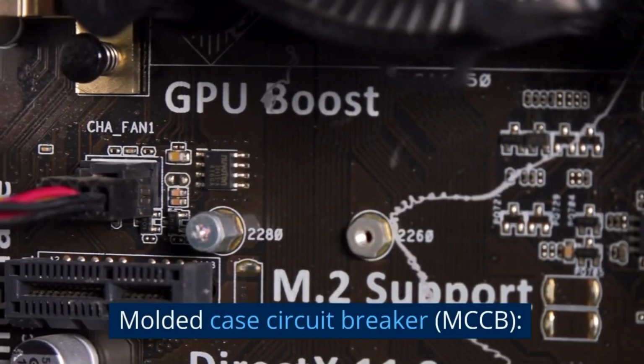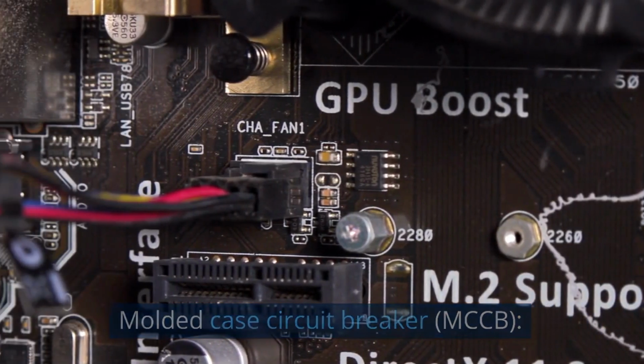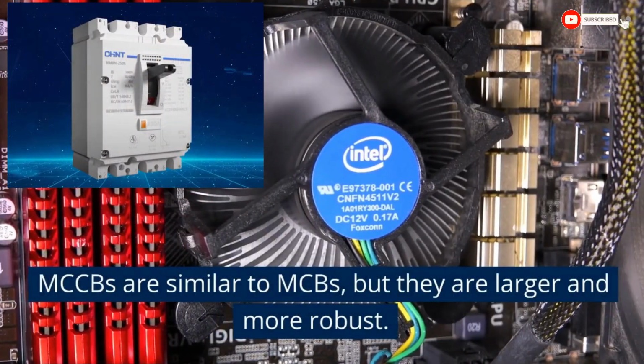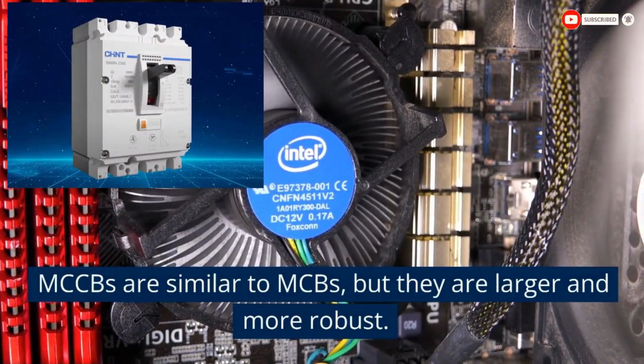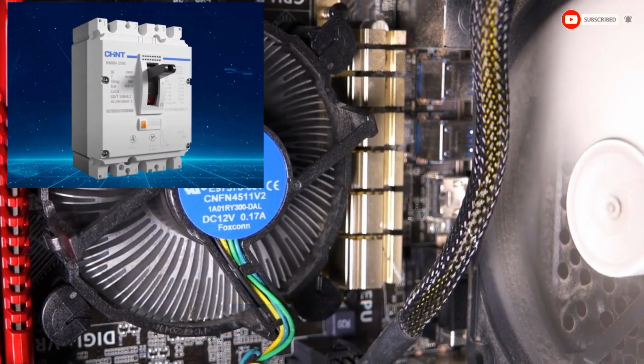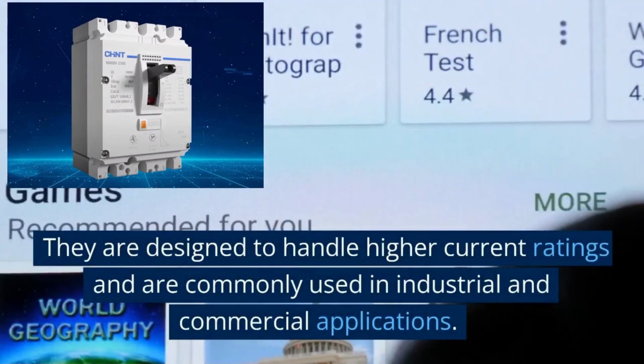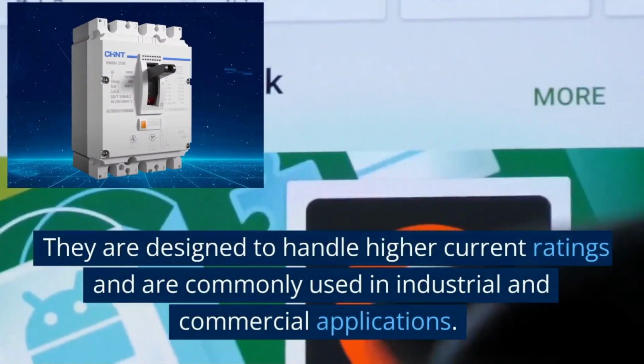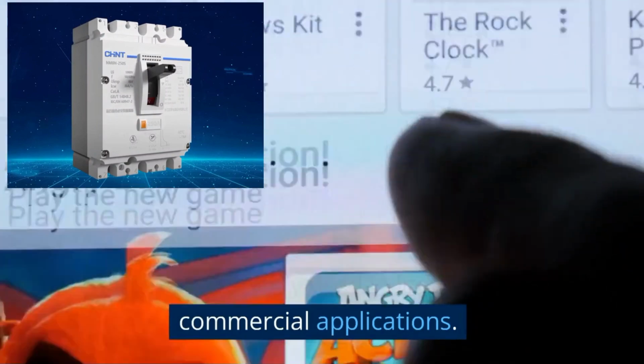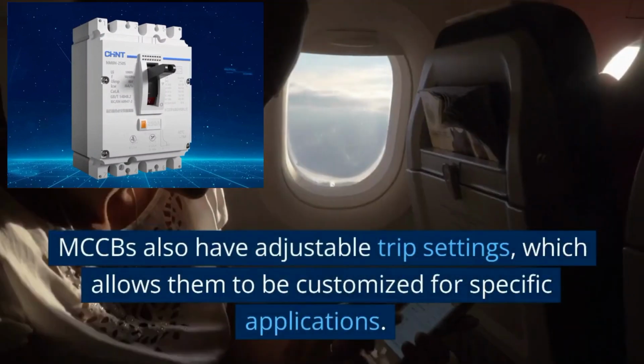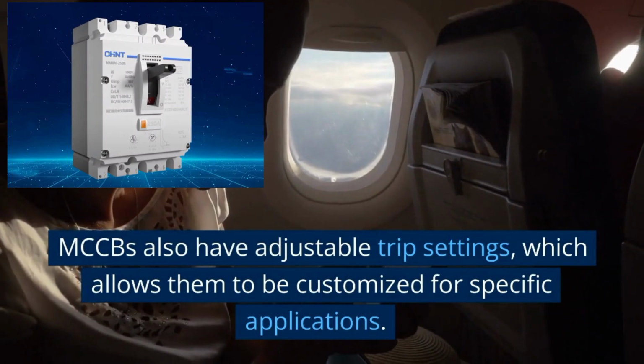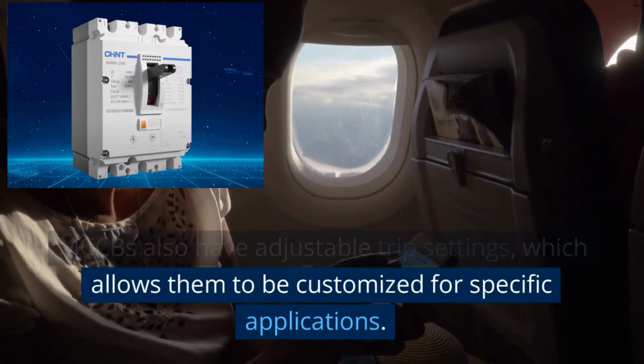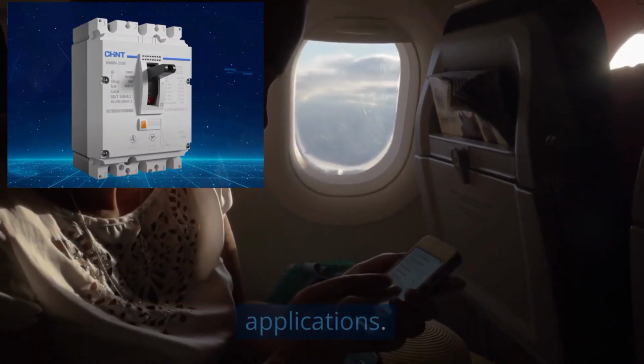Molded case circuit breaker, MCCB. MCCBs are similar to MCBs, but they are larger and more robust. They are designed to handle higher current ratings and are commonly used in industrial and commercial applications. MCCBs also have adjustable trip settings, which allows them to be customized for specific applications.